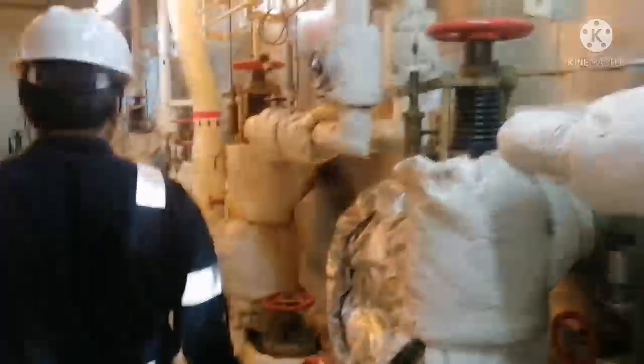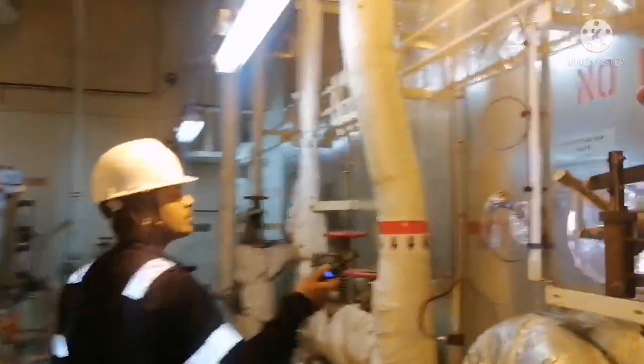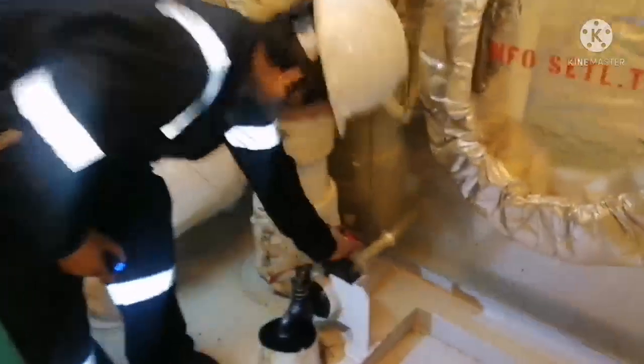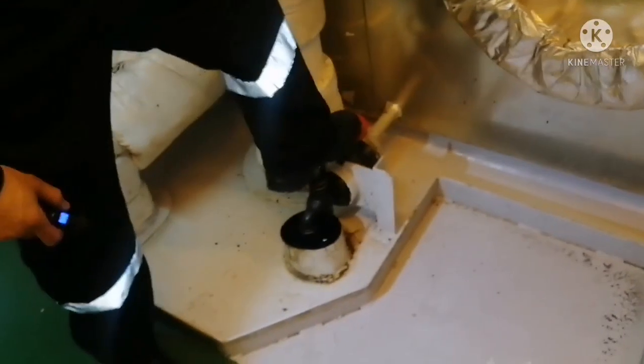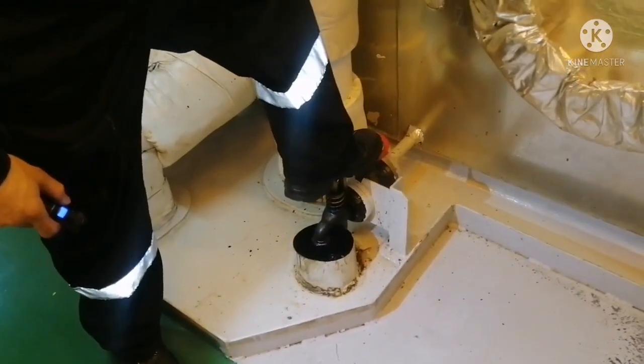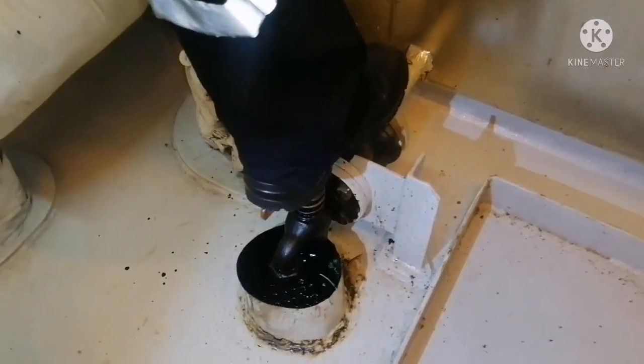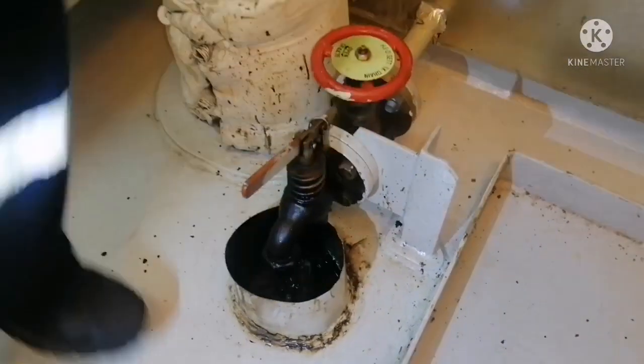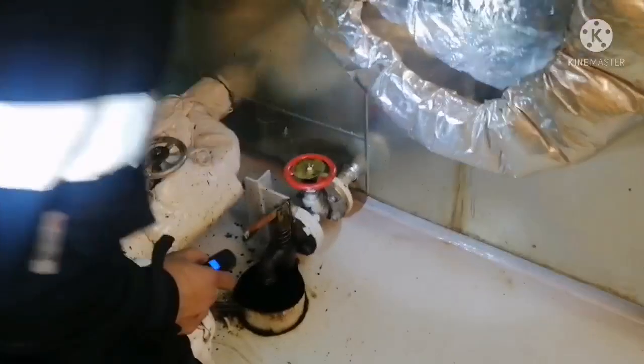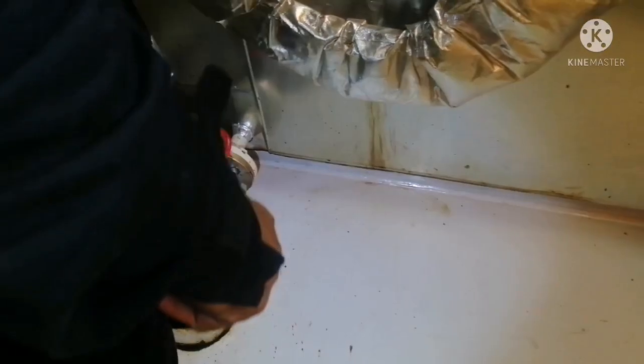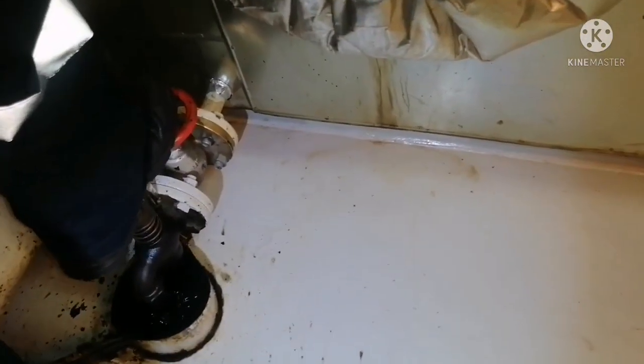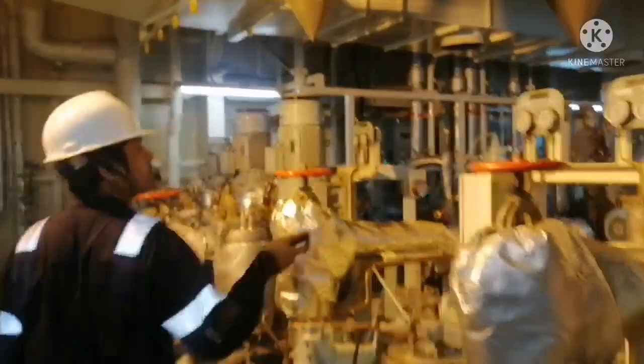So once you drain the tank, you have to ensure you are closing the drain valve. It's a spring loaded valve, so usually you have to open the valve next before the spring loaded valve, and you have to press the spring, so you can find the water coming out through the pipe. Just open the valve and press the spring, you can find the water mixed with oil will come out. Once you find only oil is coming, then you can stop draining.